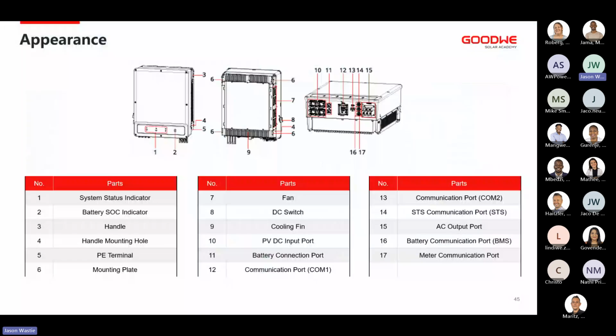Here are the parts and ports for the new inverter. You'll note that from port number 13 through to 17, there is no backup port on this inverter. All is controlled through the STS device. This is done so that the inverter can be multi-purpose, as it can be made for an off-grid inverter, minimizing the cost for the end user, and then partnered with our STS it can be used for on or off-grid applications.